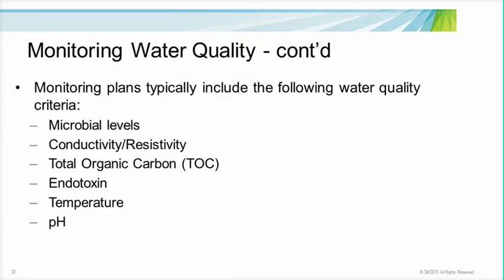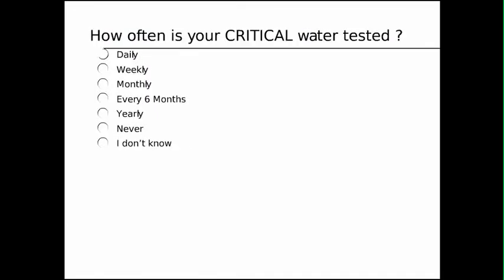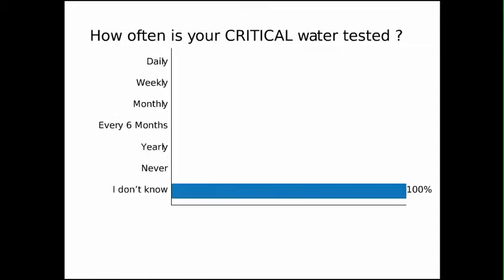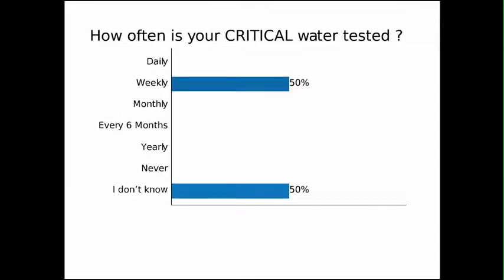Typical monitoring plans include weekly or monthly measuring of water quality criteria such as microbial levels, conductivity or resistivity, which measures the total dissolved solids or those ionic compounds, total organic carbon impurities, endotoxin, temperature, and pH. This brings us to our next polling question. In your facility, how often is your critical water tested? Is it tested on a daily, weekly, monthly period, or more long-term, as in 6 months, yearly? And of course, if you don't know, please select the I don't know button.